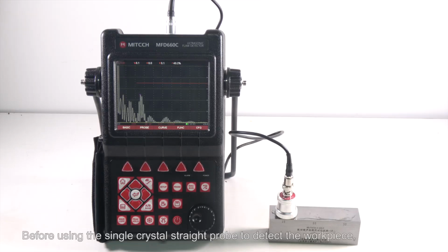Before using the single crystal straight probe to detect the workpiece, it's necessary to make a curve that assesses the defect size. The specific steps to make this curve are as follows. The probe parameters are entered into the instrument, and the probe is calibrated according to the straight probe calibration method.